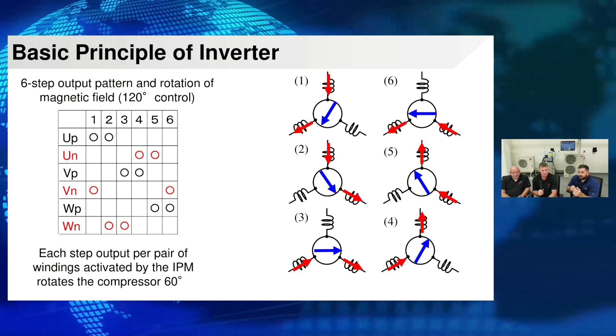We don't have to spend a ton of time on each particular side, but this is just showing a little bit more in depth what each leg is doing and how we're getting that rotation. So when we close - now you can see when we come in on the top left there, that is our IGBT. You can see your collector, your emitter, and your gate. So we close it, we feed in through our U leg, back through our V leg, and VN is closed. That's giving us that AC path, right? If it was DC, we wouldn't have the ability to always have that path back.